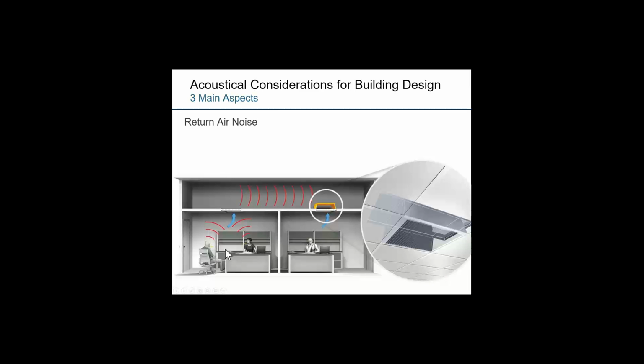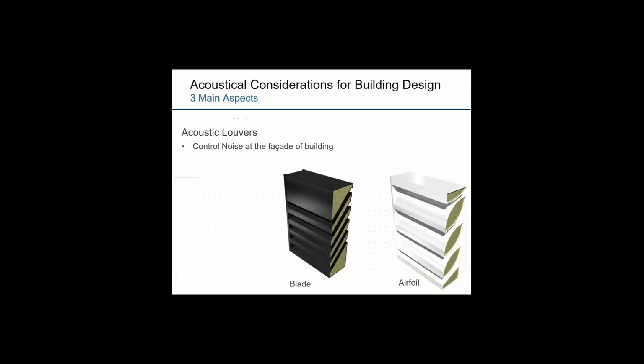An example like this here, you can sort of see how sound energy can freely transmit through and across and into return air grills. This canopy above one of those openings can help block and mitigate that common issue. Acoustic louvers are another type of noise control product that can work very well for mitigating sound transmission. Louvers in general are a great way to ventilate a mechanical space where sound and air can transmit through these louvered blades. But acoustic louvers will typically have acoustic material within the blades and perforated metal to help absorb and block that transmission of sound.